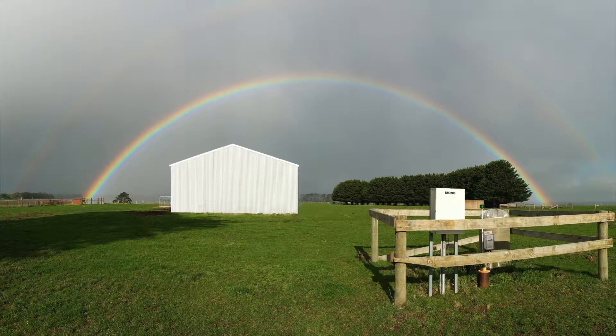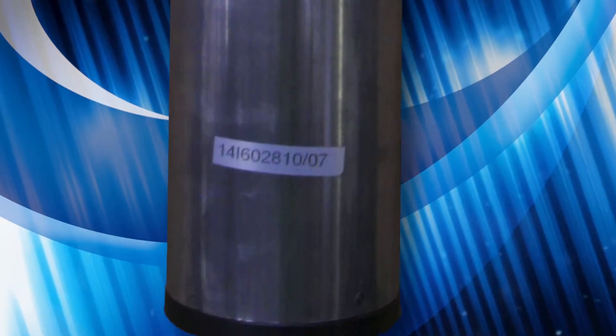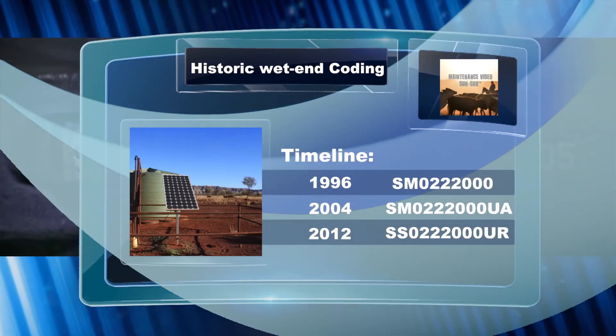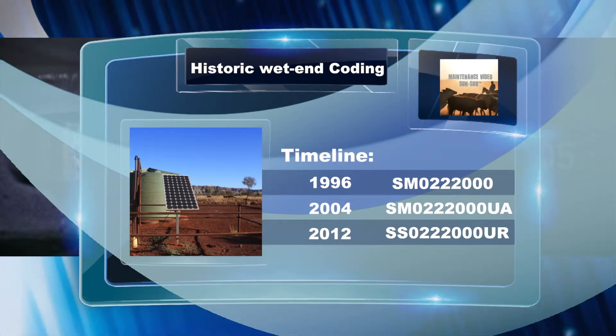To begin, you must check which model pump and motor you are repairing to ensure correct ordering of replacement components. The etching number on the motor adapter you see here was introduced in 2009. Prior to this, a sticker was attached to the motor with similar detail. On the etching, there are two different sets of identification numbers. The first set is the pump model, which you'll need to understand for what replacement components are required. As we show here, this pump coding will be on models manufactured from 2012.